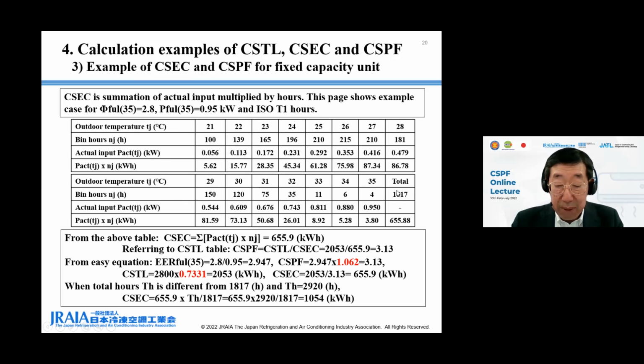The third line shows actual input at each TJ, which can be calculated as shown in the example of actual ER for fixed capacity unit. The fourth line shows the actual input in the third line multiplied by bin hours NJ in the second line, and the total of this line becomes cooling seasonal energy consumption, CSEC. From this table, CSEC is 655.9 kilowatt hour, as shown in the lower right-hand row.